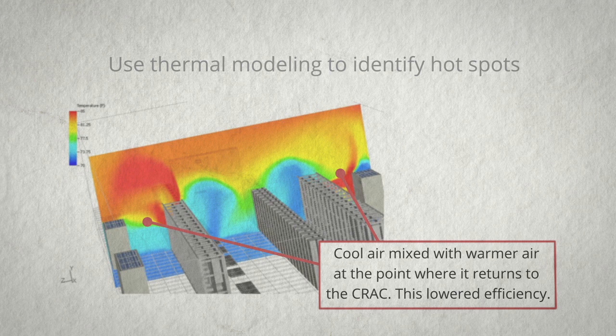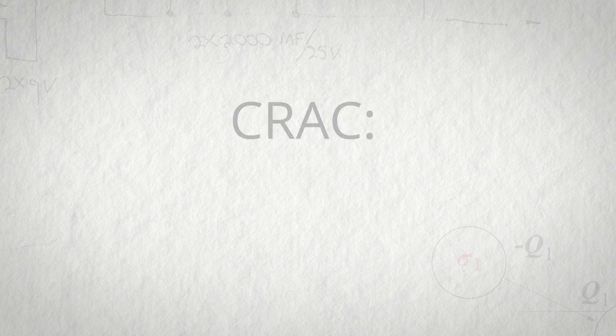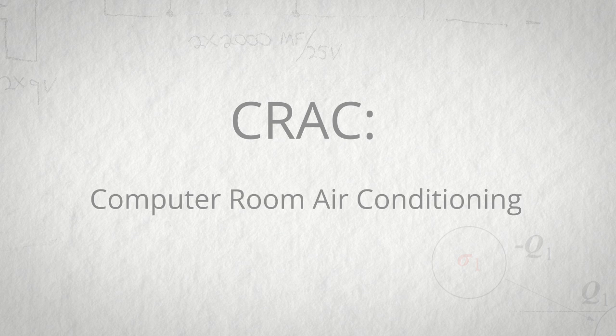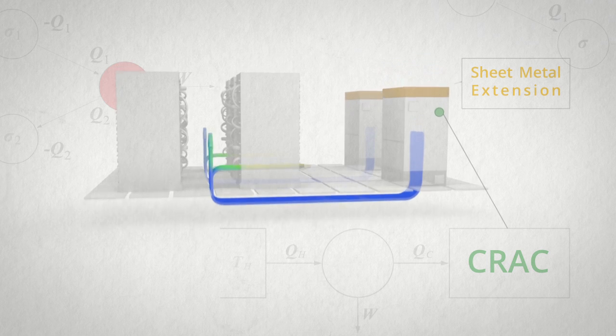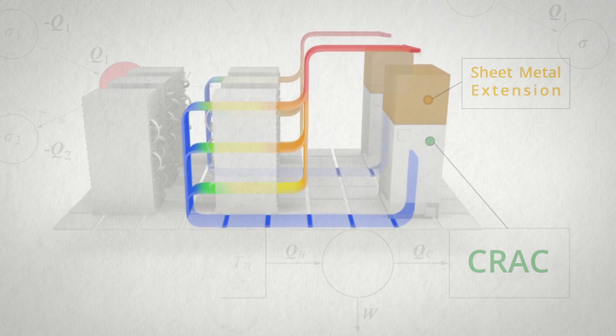For example, in one of our computing and networking rooms, we call them CNRs, we actually did some thermal modeling to see exactly what air flow was doing. Through that modeling, we realized that the intake to our CRACs was too low and that by simply piecing together some sheet metal, we could create extensions that would dramatically increase the air flow quality into the CRACs.